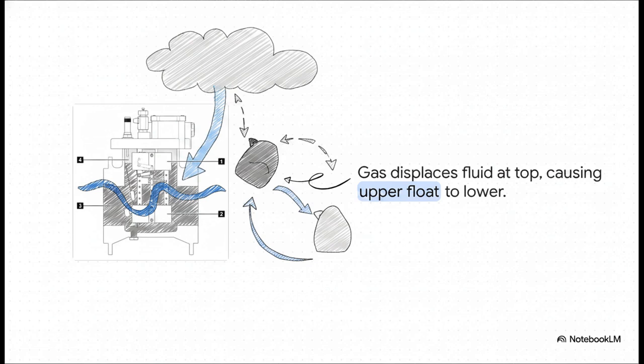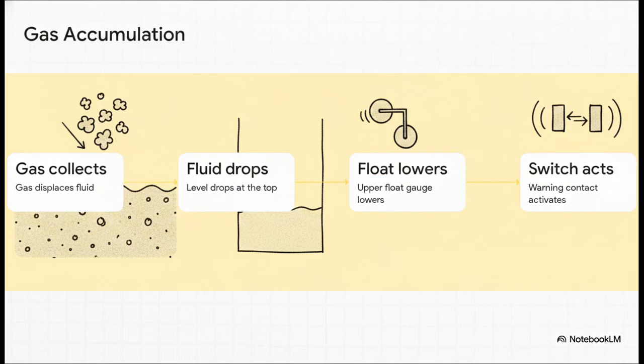And as that gas collects at the very top of the chamber, it physically pushes the insulating fluid out of the way. It forces the fluid level down, basically creating this dangerous pocket of gas right at the roof of the device. It is just a perfect cause and effect chain reaction. The gas pushes the oil down, right? And because the oil level drops, that upper float just loses its buoyancy and drops down with gravity. That simple dropping motion instantly triggers a reed-type switch, closing the contact and firing off a warning signal. The physics here simply cannot be bypassed.